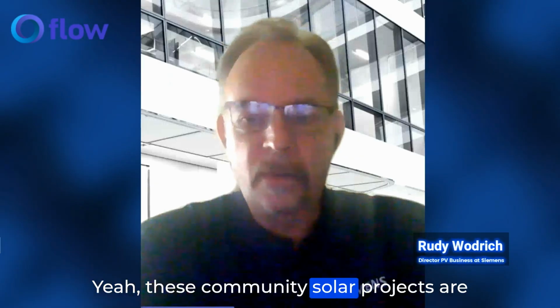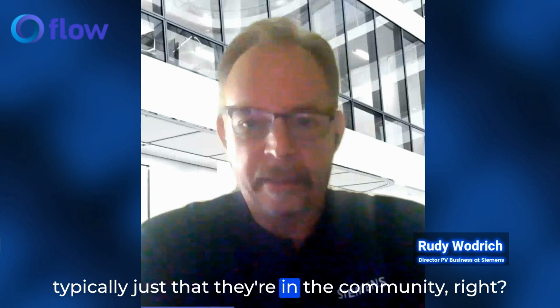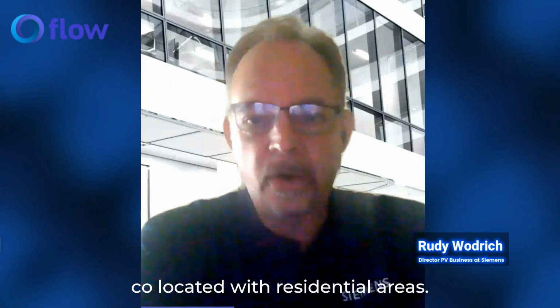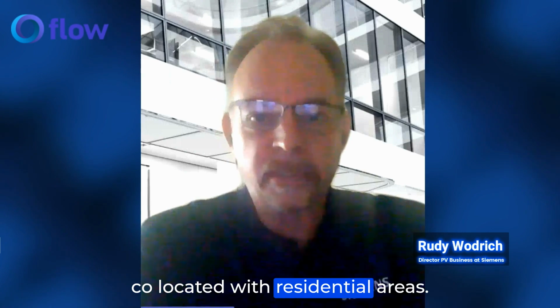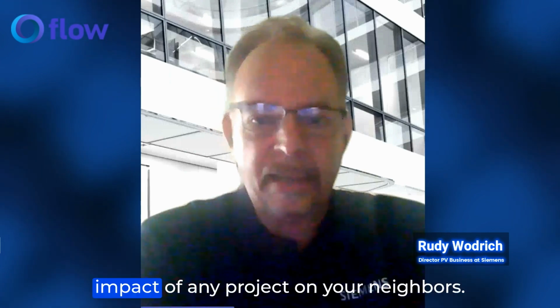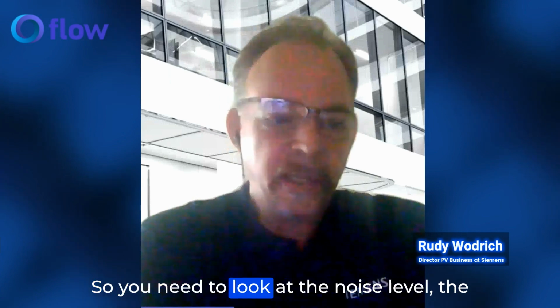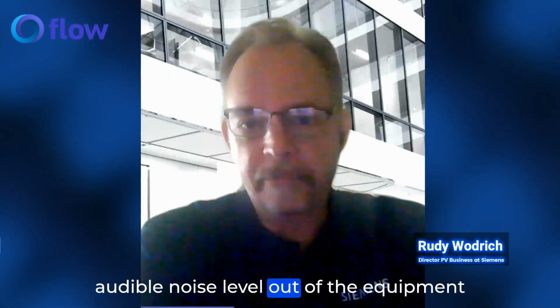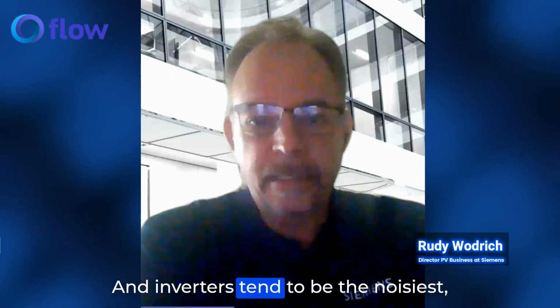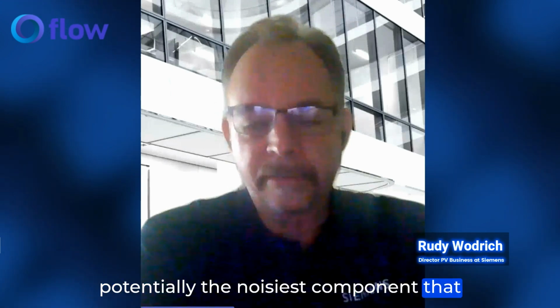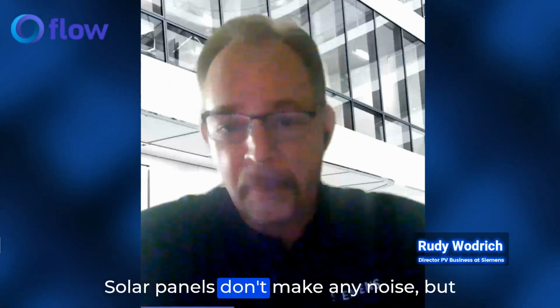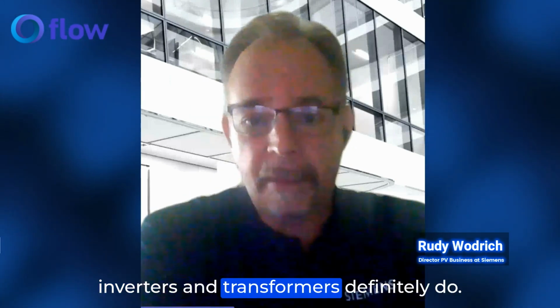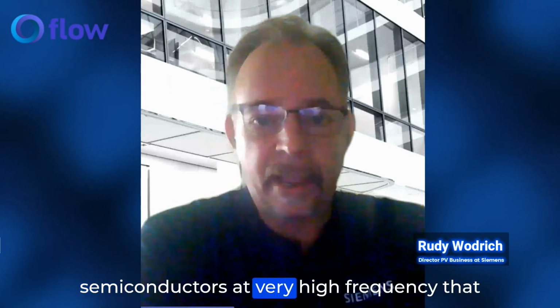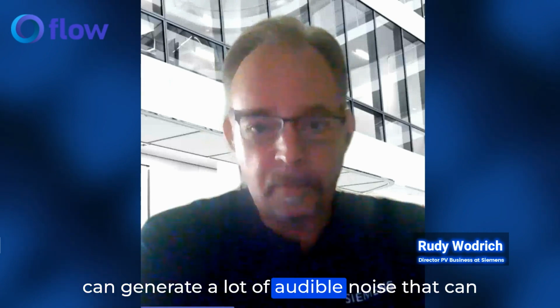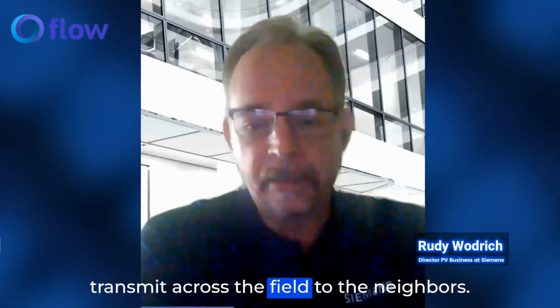Yeah, well, these community solar projects are typically just that. They're in the community, right? They are quite often located or co-located with residential areas, and it's important to consider the impact of any project on your neighbors. So you need to look at the audible noise level out of the equipment you're going to be installing. Inverters tend to be potentially the noisiest component that you're going to install on the project. Solar panels don't make any noise, but inverters and transformers definitely do. Inverters do because they're switching IGBT devices, semiconductors, at very high frequency that can generate a lot of audible noise that can transmit across the field to the neighbors.